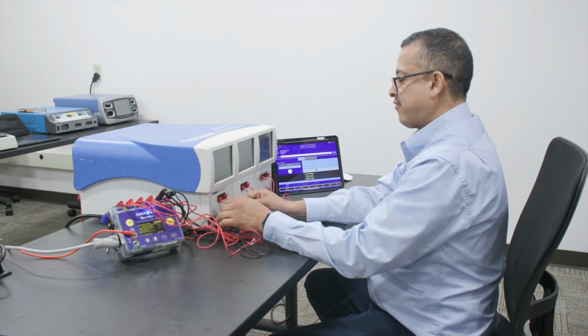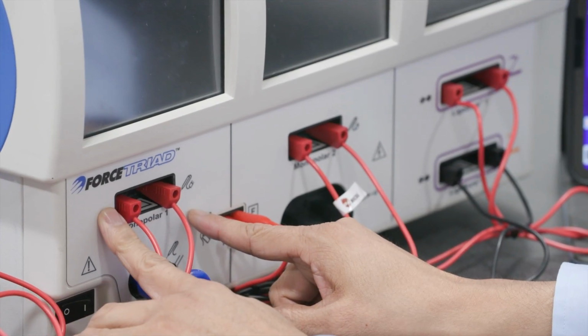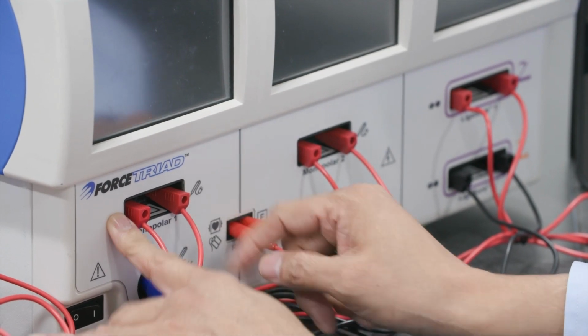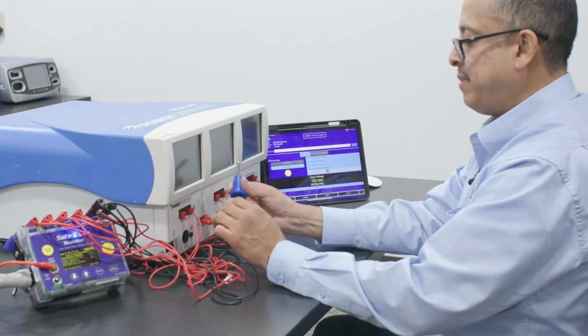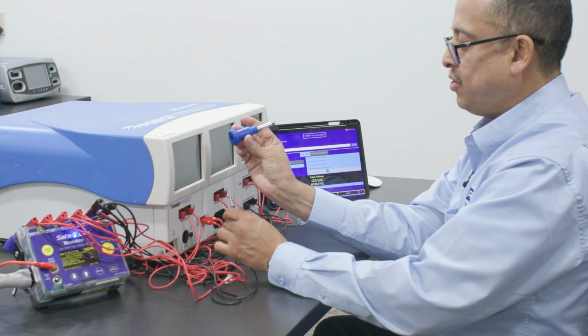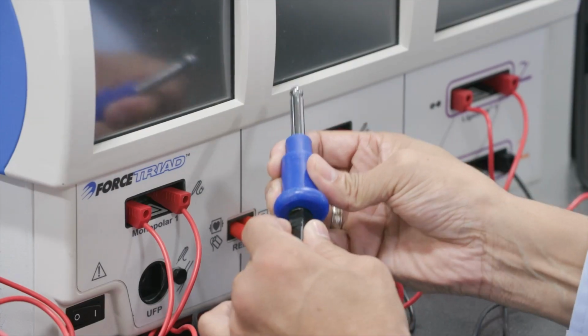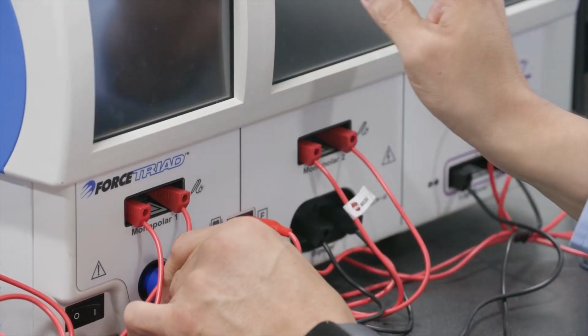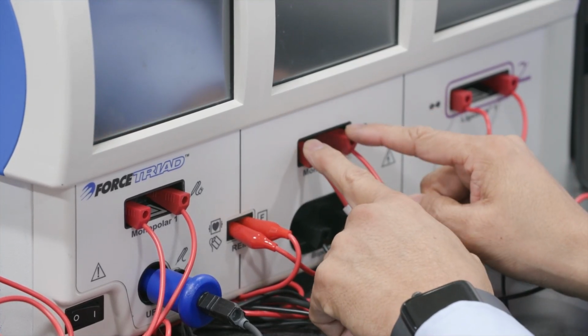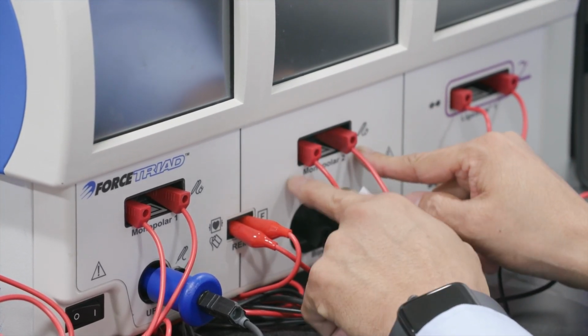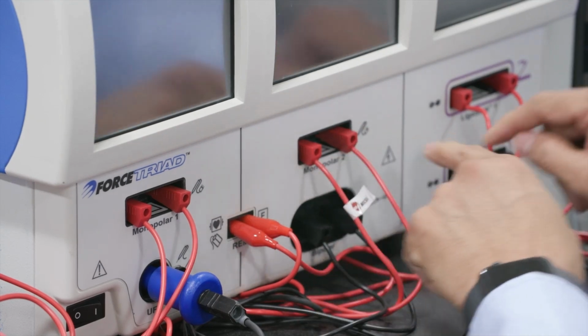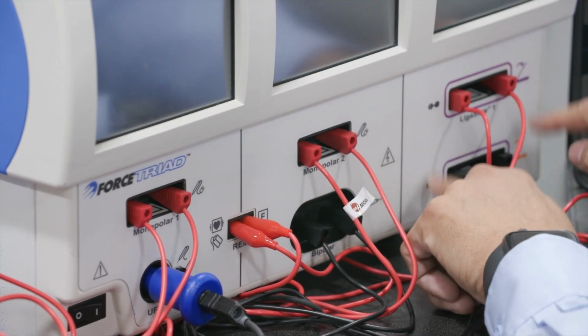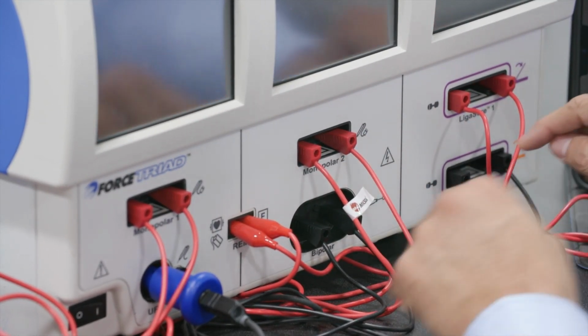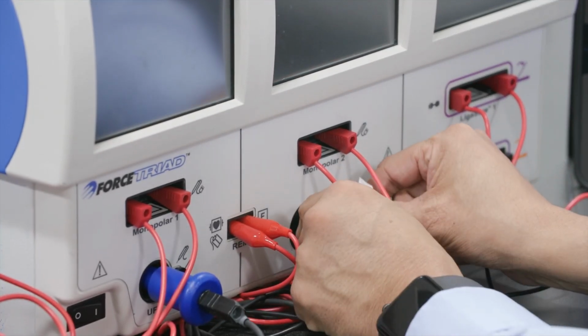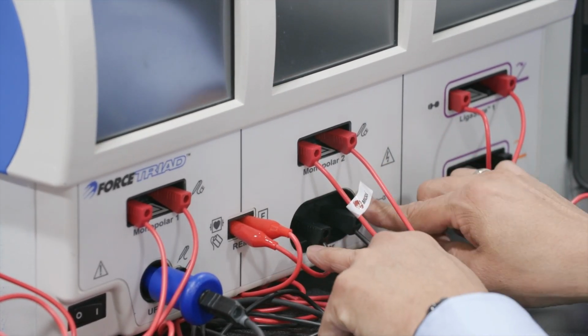And you want to do that for the monopolar one by connecting it to the very left side and then to the right side. You also want to connect your UFP using this special adapter to do that test, which you can then connect a banana plug to it and plug that in there. And then we also want to do the same banana plug connections for monopolar 2, left side and right side. Same for the third port over here on the right and the lower one as well. And then you have your bipolar port. You're going to do the same thing, connecting it to the far left and to the far right.